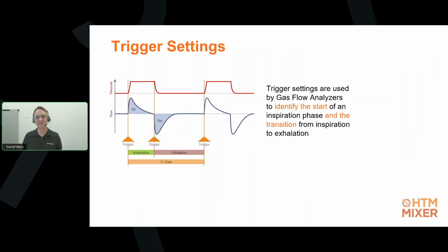So the other critical settings of gas flow analyzers you probably have heard already are trigger settings. As most of you will know, gas flow analyzers do not only measure flow rates, volume and pressure, but they can also interpret the flow and pressure waveforms and then calculate so-called breath-based parameters. If you are involved in ventilator testing, I'm sure you've seen test setups where you run a ventilation on a test lung and then verify things like tidal volumes, respiratory rate, or for example, a peak inspiratory pressure. So to measure and calculate these breath-based parameters, the gas flow analyzer needs to be able to determine the breath phases, meaning to know when a new breath phase starts and when it transitions from inhalation to exhalation.